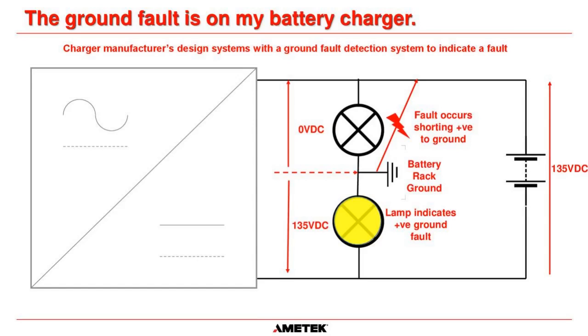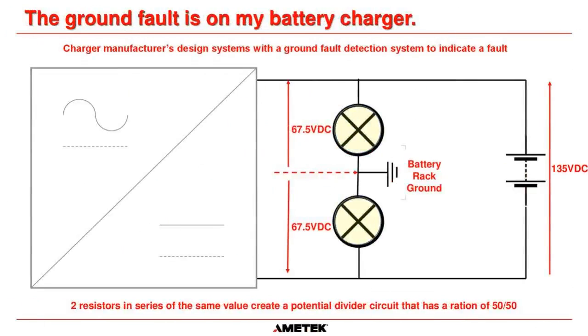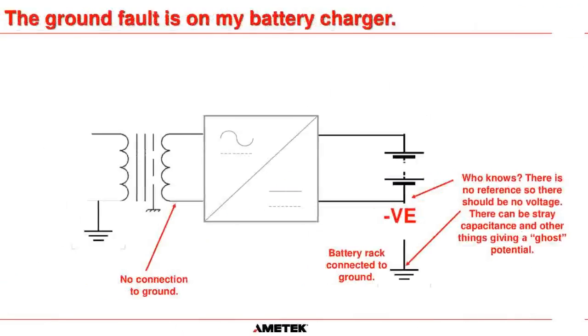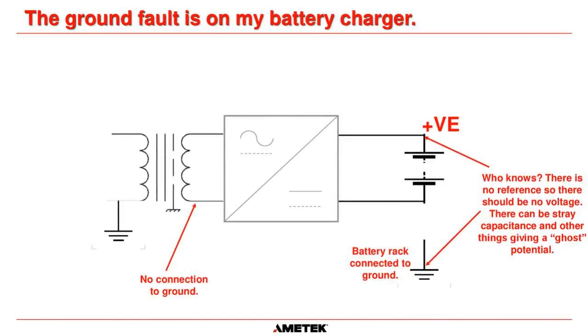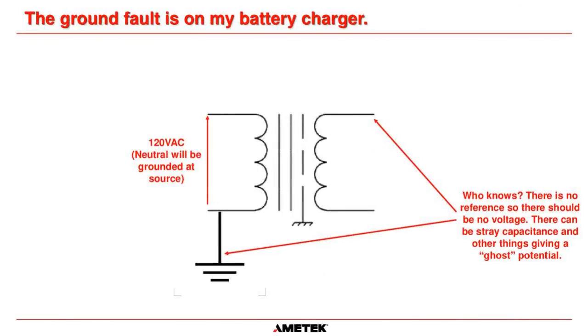It's only when you get another ground fault on the other pole that you are going to have an issue. And that goes back to the picture where I said the man could actually touch one side. If you really wanted to buck trends and do weird things, you can connect the hot or the live of a secondary of an isolation transformer to ground if you wanted to. Okay, it's only when the other pole then has a ground also that you have a direct short circuit between the two, and it would cause things to trip. Hopefully that explains that question.